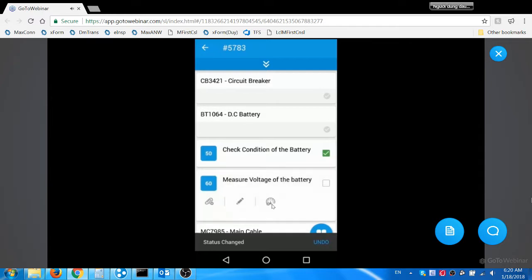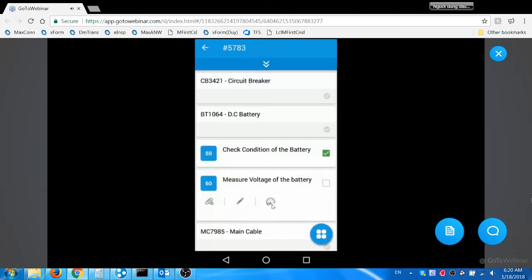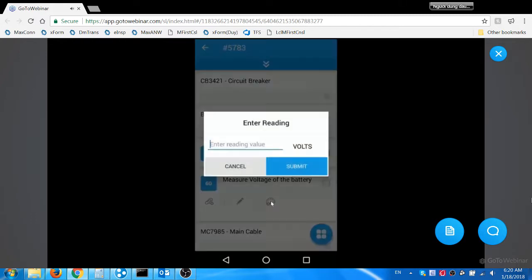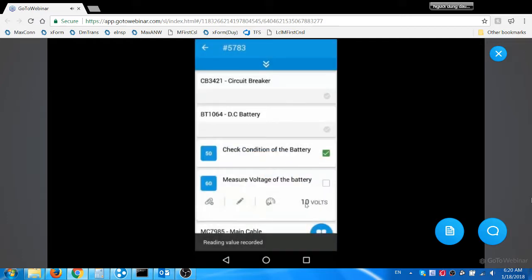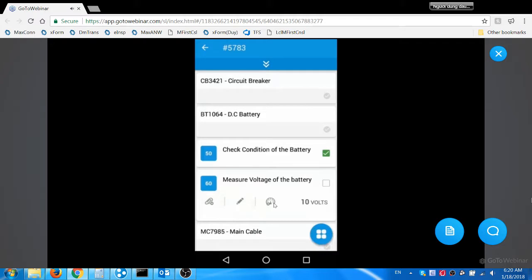He enters the measurement readings for the second task by clicking the measurement icon. He enters the value as 10. The measurement icon is displayed only if any condition monitoring point is associated with the task. The entered values are updated in the respective condition monitoring point in Maximo. If the entered value exceeds the control limit set, Maximo generates the corrective maintenance work order to fix the issue.